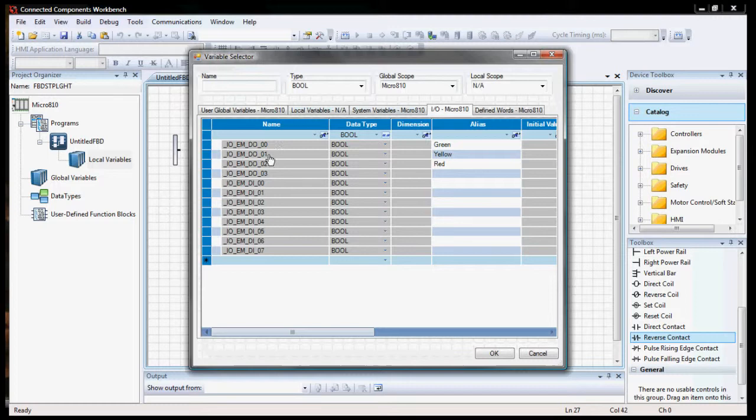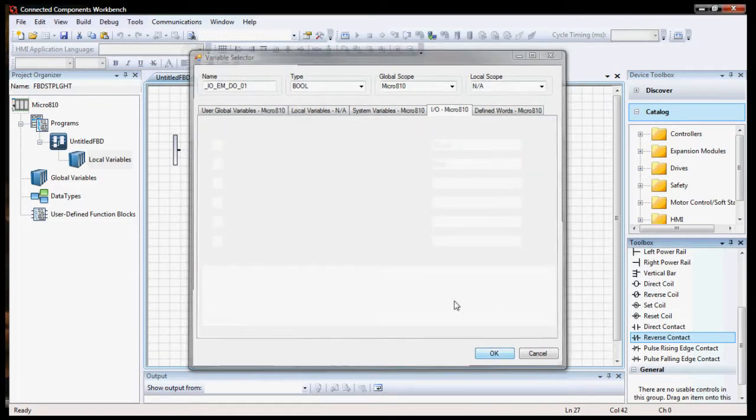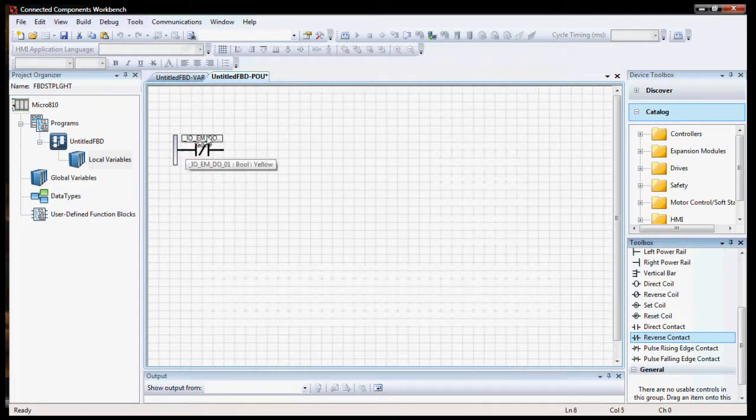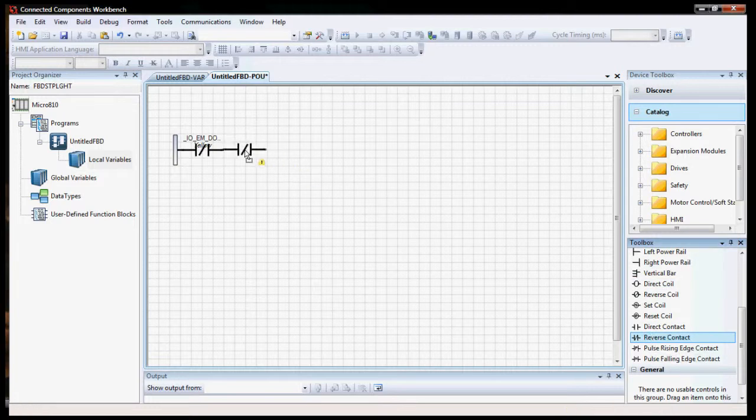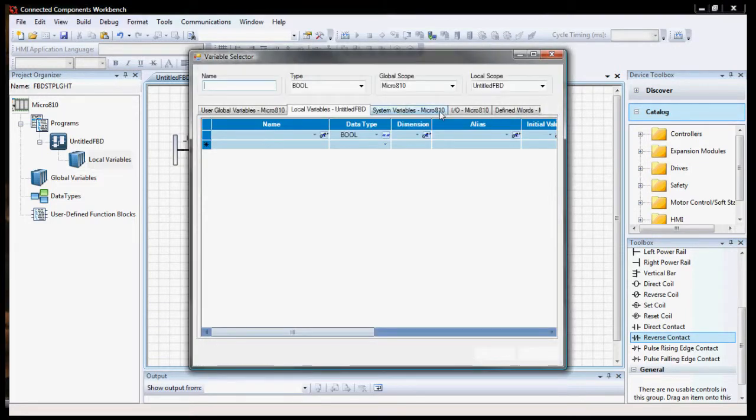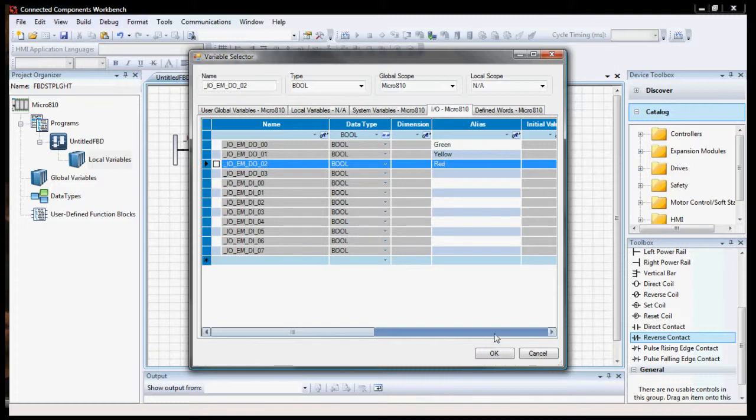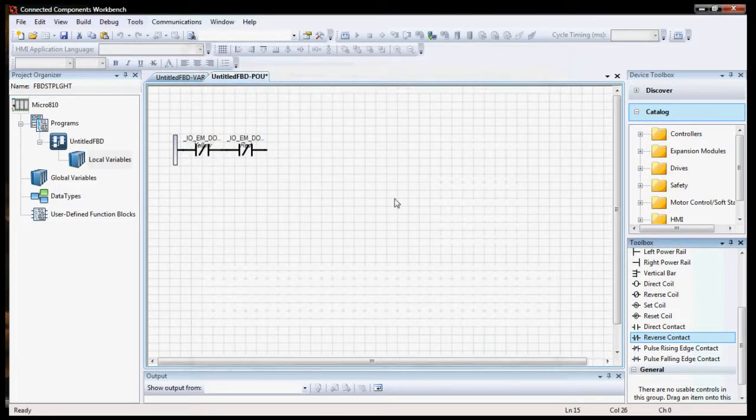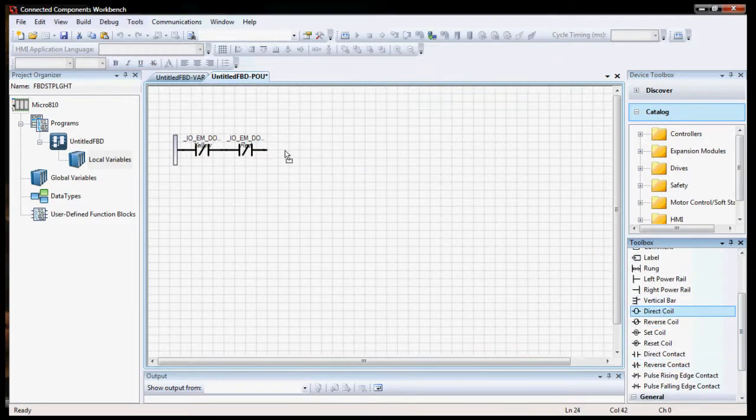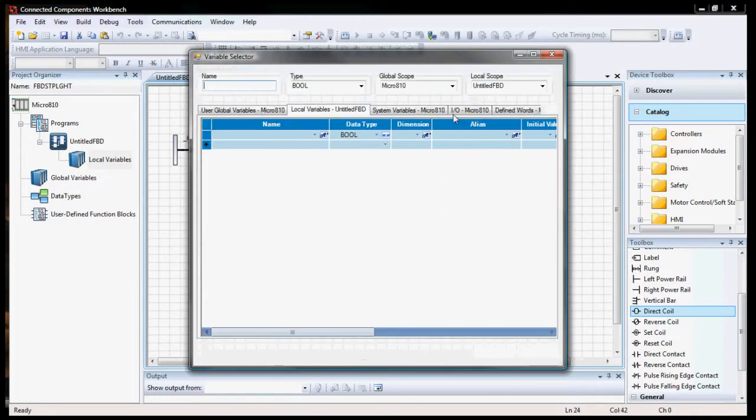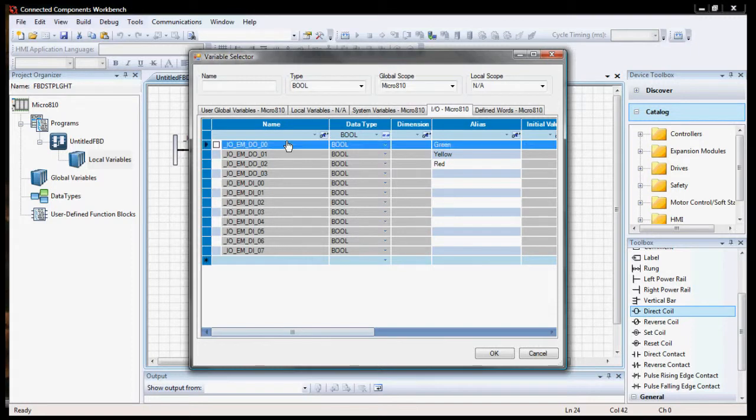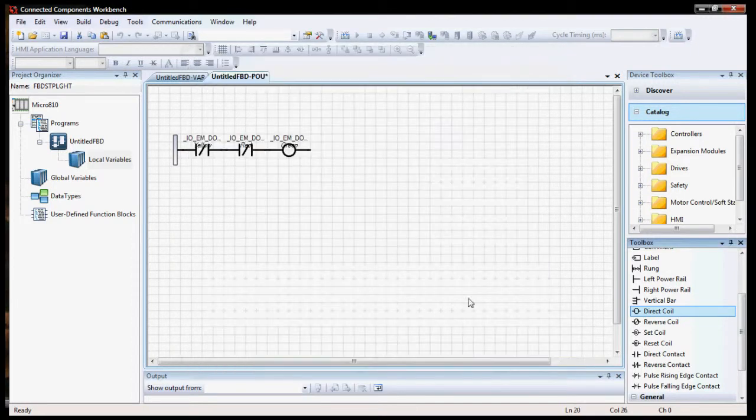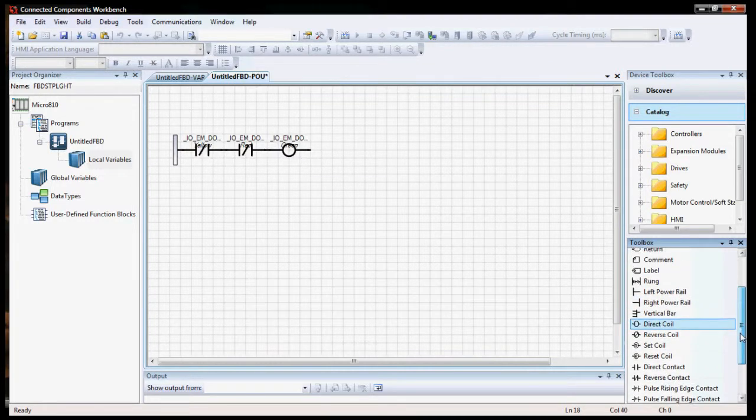So our yellow light is digital output 1 and I put in here the names of the aliases so that it's easier to tell what's going on. So we have our yellow there and it's displaying both that and yellow, but it's yellow. Let's grab another one for red. And then we want when those two are not on, then we'll have our green on. We're going to do a direct coil for this one. So when either of these two turn on, then this is false and the green light is off.